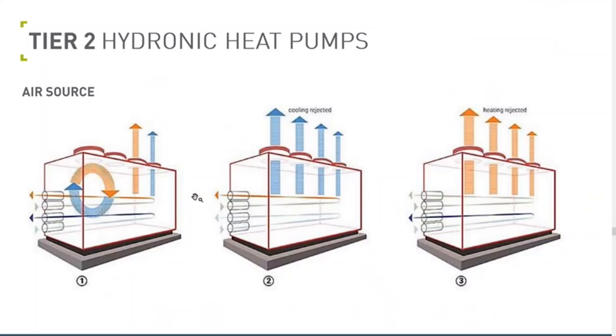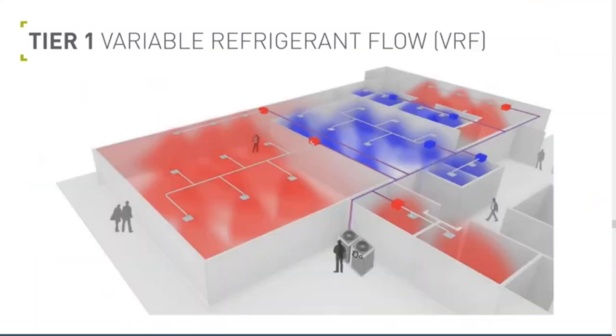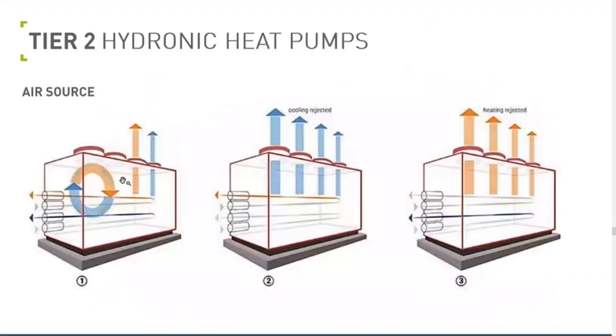The hydronic heat pump is very similar to this system, except instead of transporting refrigerant inside the building and running it through a fan coil, that entire system is going to be located and centralized, probably on a rooftop somewhere, maybe outside or maybe in a basement, as long as it has airflow. The refrigeration cycle is all inside that unitized system, and it's generating hot water and pushing that hot water through the building. Same thing, you're just running air over those coils. The coils are filled with hot water, and that's how you're getting heating for those systems.